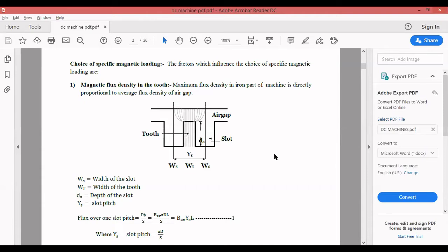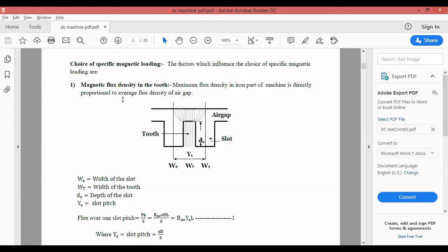For the DC machine, a few things will be common but other things can be added for DC machines, and likewise for synchronous machines and induction motors. The factors which influence the choice of specific magnetic loadings: the first one is magnetic flux density in the teeth. The maximum flux density in the iron part of the machine is directly proportional to the average flux density in the air gap.